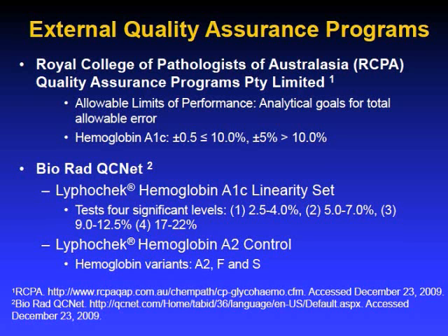It is very important that external quality control testing is required wherever methods are being used to measure A1c levels. Appropriate quality control will require the methods being used to have small coefficients of variance and high precision. Each lab should prepare and purchase their own quality control specimens and set their own limits and acceptance criteria for the specific laboratory setting that they're in.